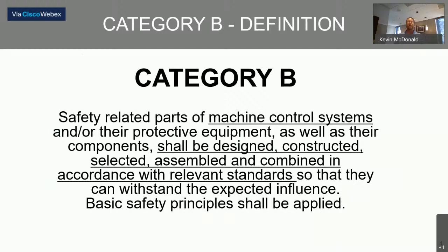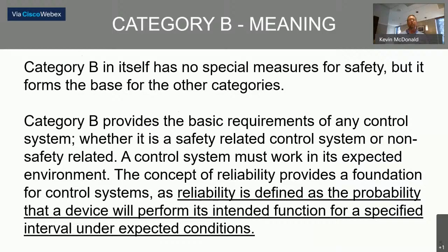The first category is Safety Category B. It states: machine control systems shall be designed, constructed, selected, assembled, and combined in accordance with relevant standards. Category B is really not a safety category per se — it's best engineering practices, where we follow standards and codes such as NEC or NFPA. Everything in Category 4 includes everything in Categories 3, 2, 1, and B, so B becomes our foundation for good practices.